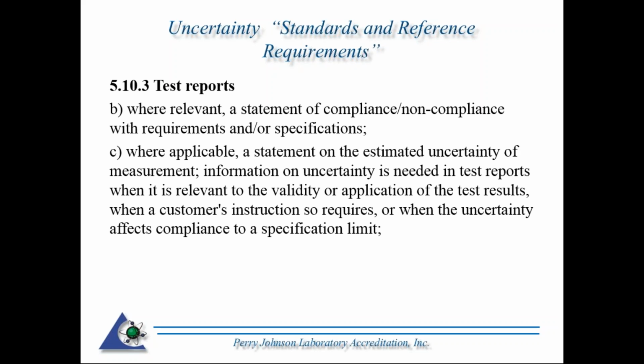Still on 17025 test reports. Where relevant, a statement of compliance, non-compliance with requirements and or specifications. Again, with that, when you're making a statement of compliance with the testing lab, you too will have to look at the uncertainty and basically take that into account. Where applicable, a statement on the estimated uncertainty of measurement. Information on the uncertainty is needed in test reports when it is relevant to the validity or application of the test results, when a customer instruction so requires, or when the uncertainty affects compliance to a specification limit.